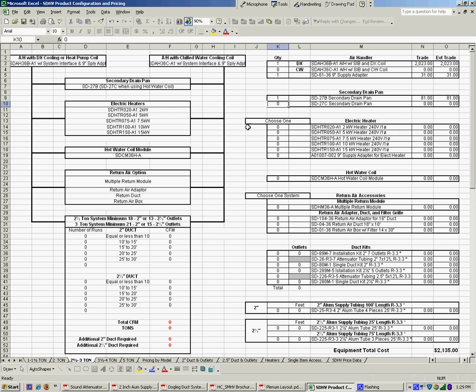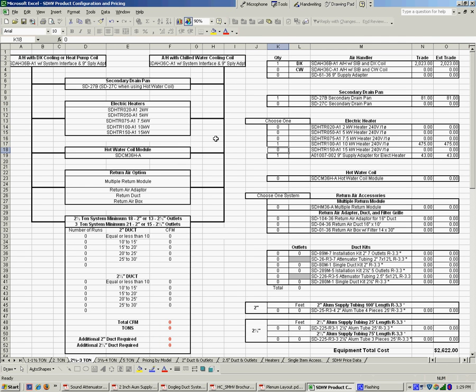We have the option of adding electric heat to these systems, so we can do it from 2 to 15KW on the 3-ton system. So let's put in a 10KW. And you'll notice it also picked up the adapter off of that also and eliminated the one above. So we're not duplicating that. We have the option of adding a hot water coil to that. We're not going to do that since we're going to do electric heaters.